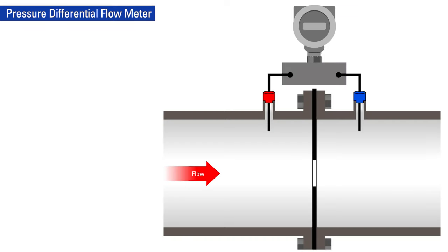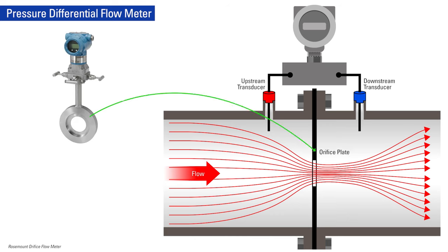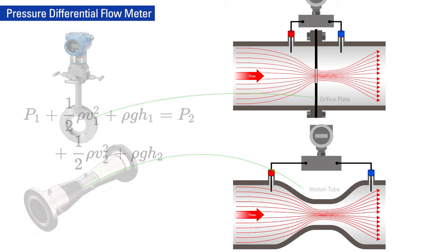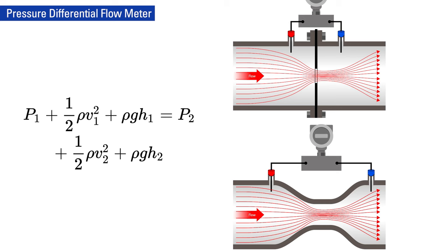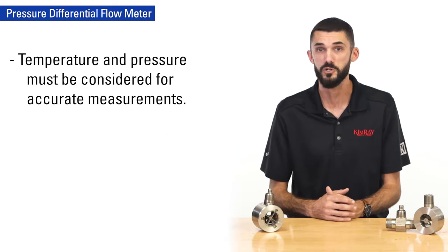The third type of flow meter we'll talk about is a pressure differential meter. A pressure differential meter operates by measuring a pressure drop across a fixed obstruction inserted into the flow path. Both orifice plates and venturi tubes operate by restricting flow, which causes pressure to drop. The pressure differential created allows flow monitors to determine the flow rate using Bernoulli's equation. Temperature and pressure must be considered for accurate measurements.